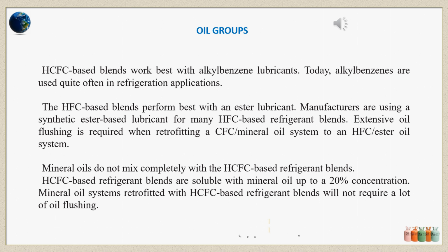The HFC-based blends perform best with an ester lubricant. Manufacturers are using a synthetic ester-based lubricant for many HFC-based refrigerant blends. Extensive oil flushing is required when retrofitting a CFC mineral oil system to an HFC ester oil system.